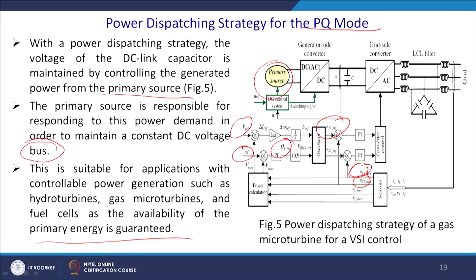This control scheme is similar to the isochronous speed control in the case of the classical DG. So, it has a synonymous in that sense, but it has got no inertia. So, this is one of the challenges of this speed control for the classical DGs, and the role of the DC bus is equivalent to the inertia, and is provided by the DC voltage constant. So, DC voltage constant, it is something like the capacitors.